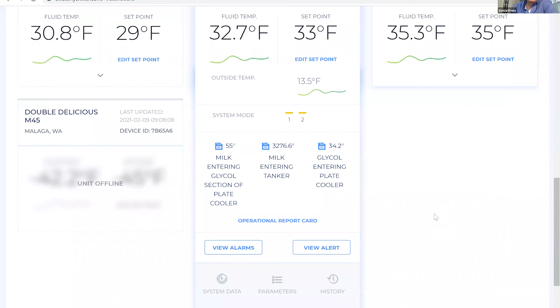So he's able to regulate his flow, and what's happening during the milking process is he's going from 98-degree milk over to the glycol section at about 60 degrees. That's tremendous, we can look at that. It measures the efficacy and how well we're doing recovering heat on that system, and manage it to the best of our ability. Going back here to the Trost dairy, we can look at our set points, the fluid temperature, and the milk going out.